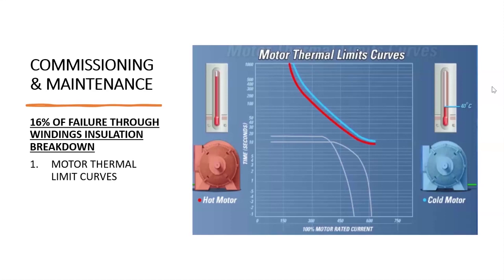So for a cold motor at about 600% of the rated current, from the chart, it can stand up to close to 20 seconds. But for a hot motor, it can stand up to close to maybe 10 seconds. It will fail.